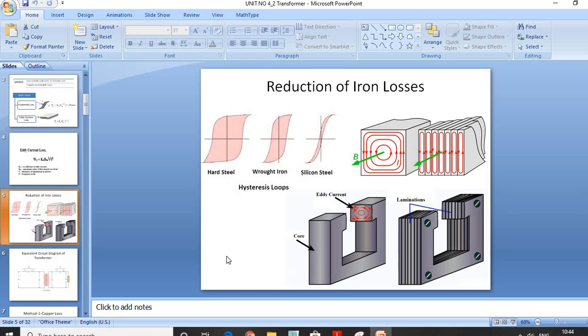To reduce Eddy Current Losses, compare a solid core and a laminated core. In solid cores, the number of Eddy Currents is more, so Eddy Current Loss is higher. In a laminated structure, varnish is placed between two laminations, which reduces the overall effect of Eddy Currents. Therefore, to reduce Eddy Current Loss, we use laminated structures.